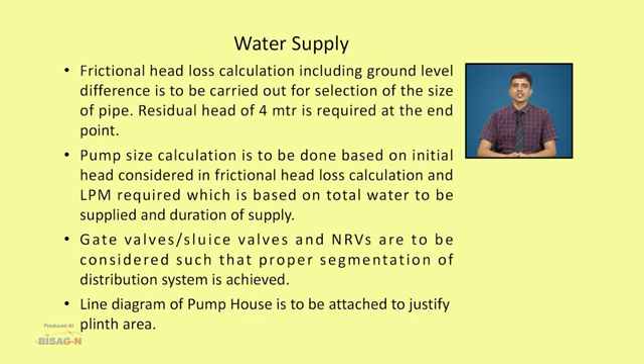Pump size calculation is to be done based on initial head considered in frictional head loss calculation and LPM required, which is based on total water to be supplied and duration of supply. Gate valves or sluice valves and NRVs are to be considered such that proper segmentation of distribution system is achieved. Line diagram of pump house is to be attached to justify plinth area.